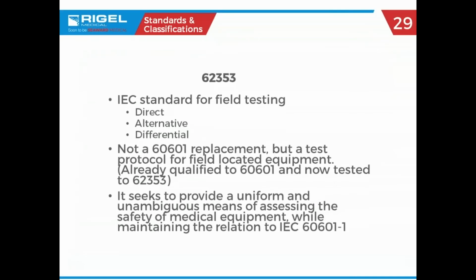Excuse me, I thought you said you weren't doing reverse polarity anymore. So 60601 is still part of it. As we start getting into other tests like NFPA 99, we don't do it here. There are some biomeds out there, older ones, gray hair like me, that still like to do reverse polarity. Some manufacturers require us to do that, like Philips, for instance, on the V60s. They actually require you to do the full test. So don't go back and say Jack said that we no longer do it.